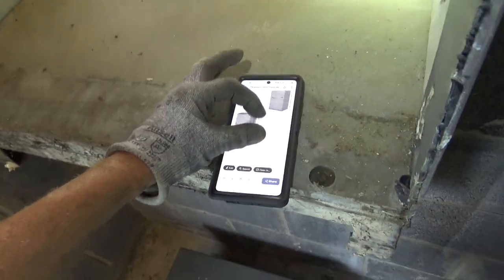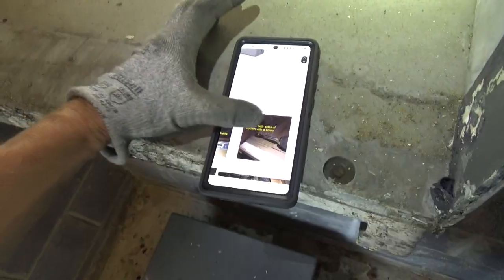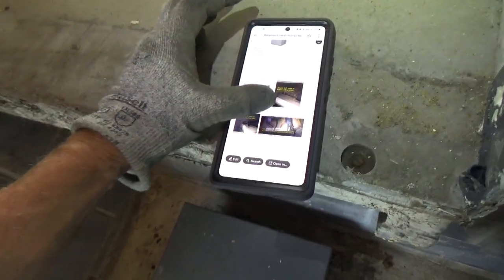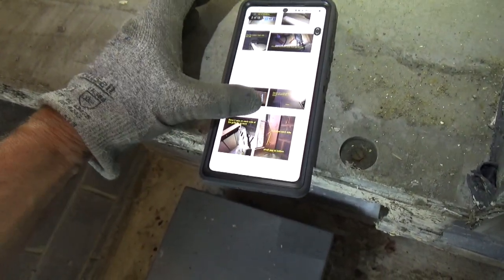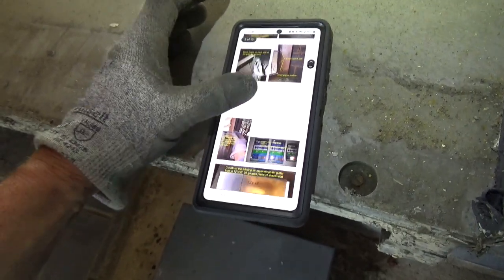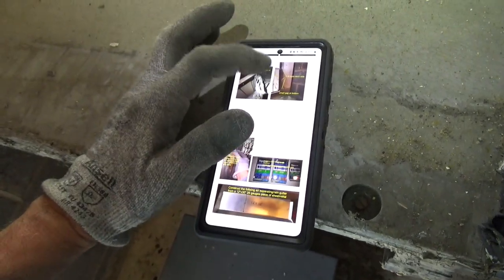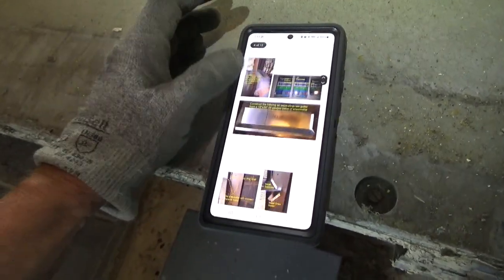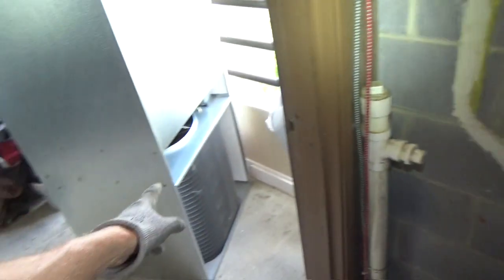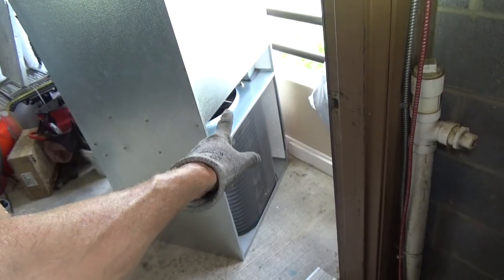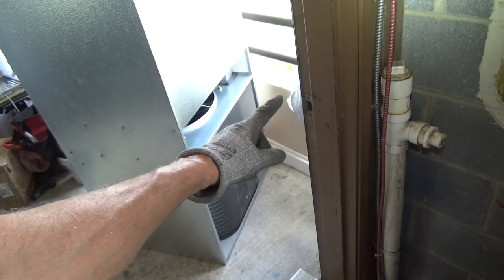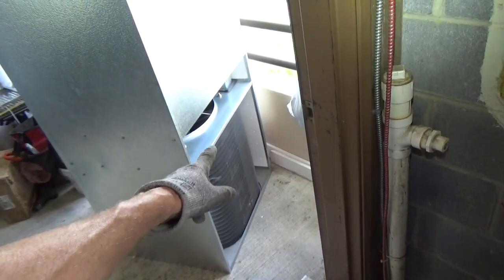So I need to make this the same as my install document, which I made just so I don't have to remember what to do. And it's a step-by-step. I show with the old grill. But the main thing is you want to have your air separator right there so your condenser air goes out of the building and not back into the condenser coil.